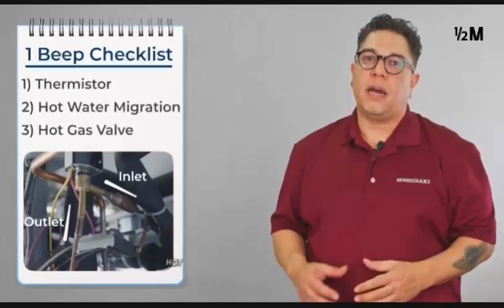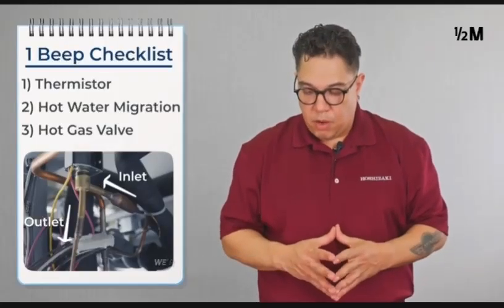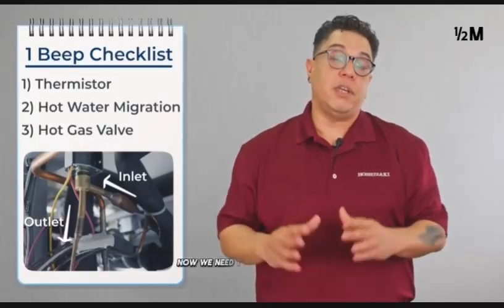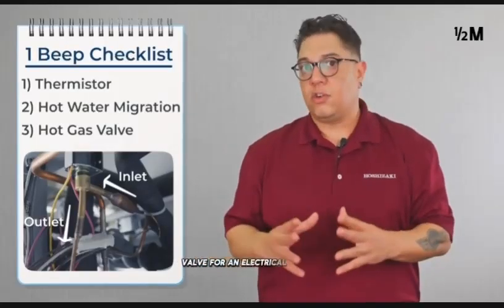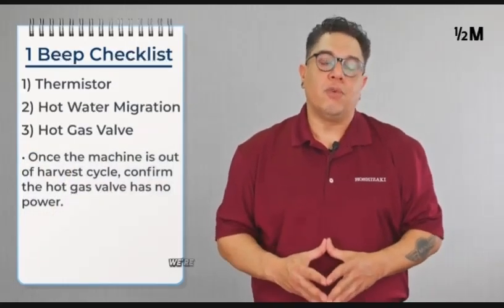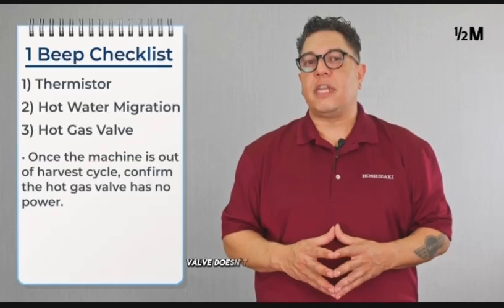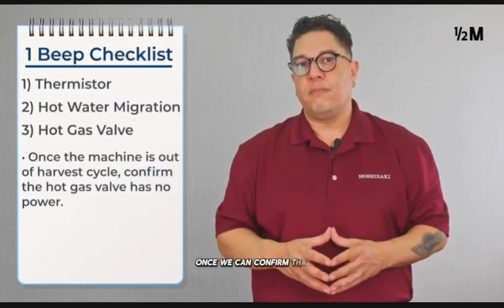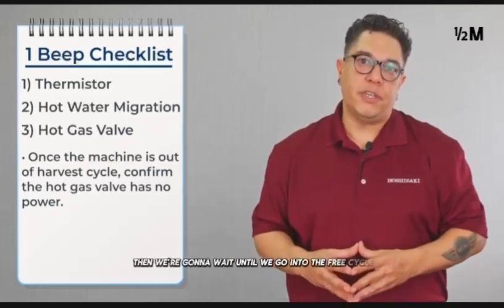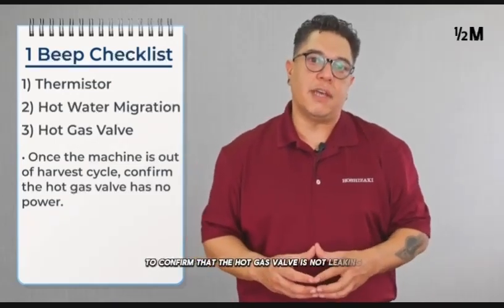After we confirm that hot water migration is not the problem, we're going to go and check the hot gas valve. Now, we need to check the hot gas valve for an electrical problem or a mechanical problem. Once we come out of harvest, we're going to confirm that the hot gas valve doesn't have any power. Once we can confirm that, then we're going to wait until we go into the freeze cycle to confirm that the hot gas valve is not leaking by.